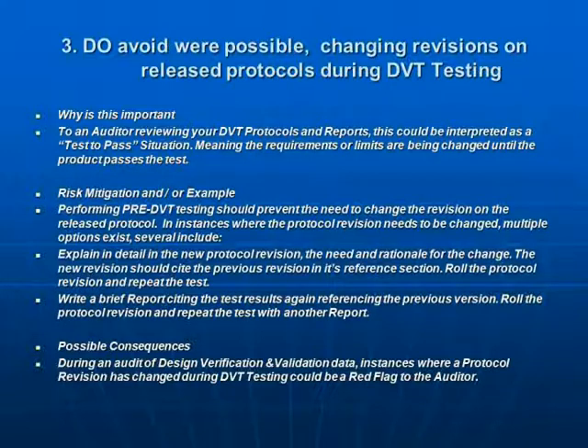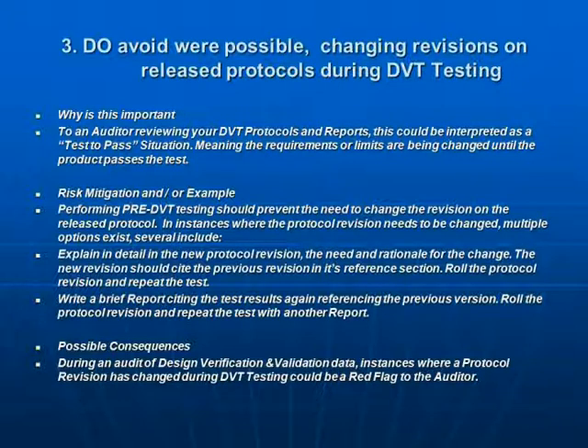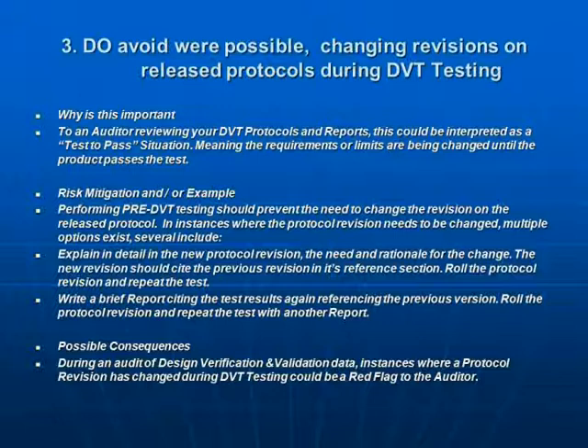The third issue discusses protocol revisions on released DVT protocols. Performing pre-DVT testing is one way to minimize the need to change revisions on protocols. Once a protocol is formally released, changing the revision during a concurrent series of DVT tests could be interpreted as a test-to-pass change. So it's critical that the initial test results be documented in a report and that these results be referenced in all subsequent reports.